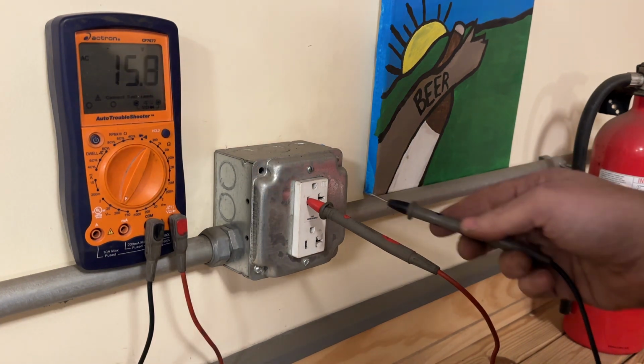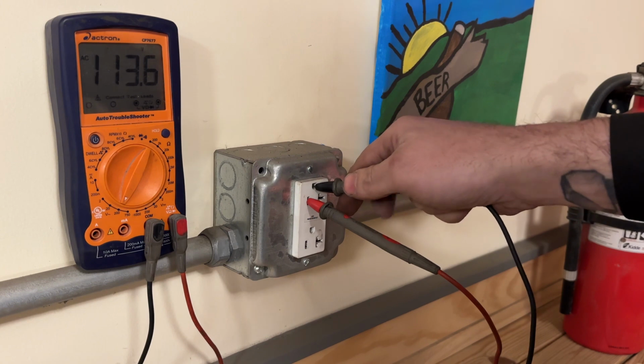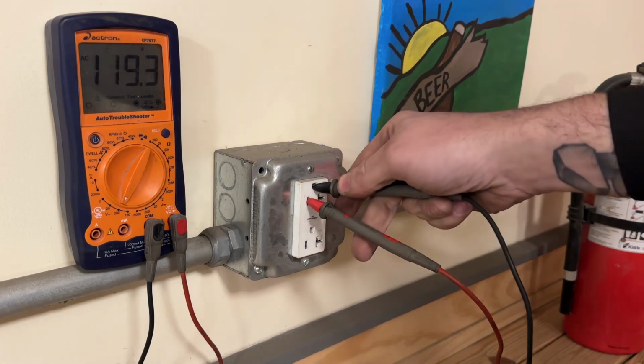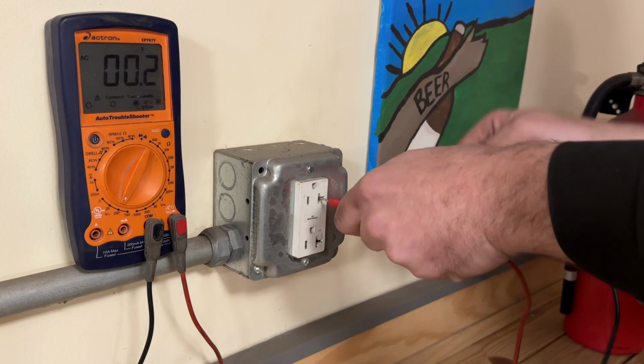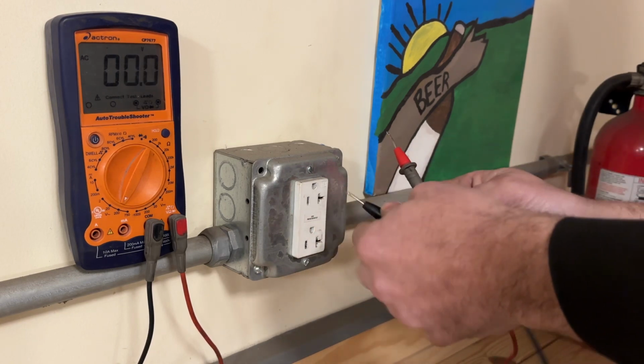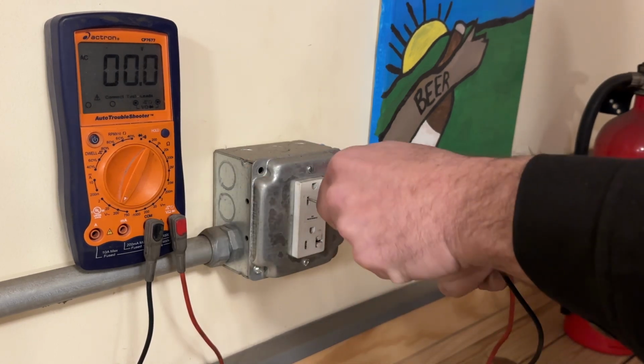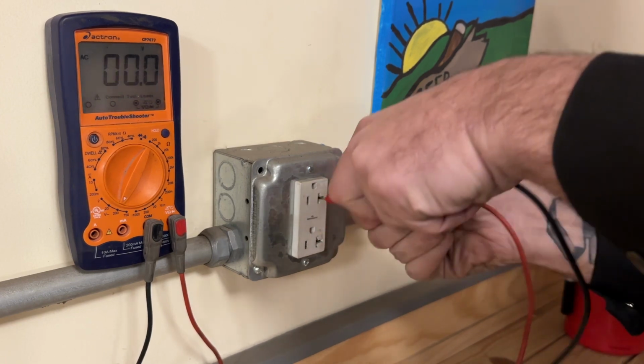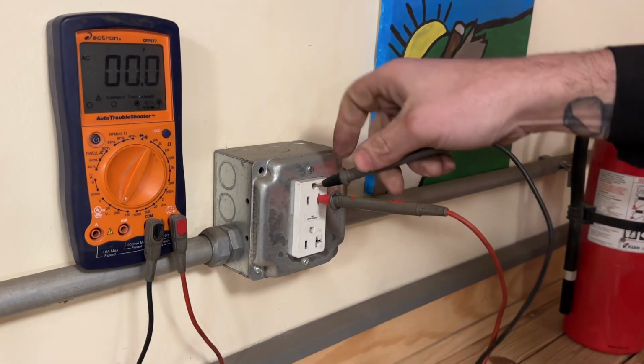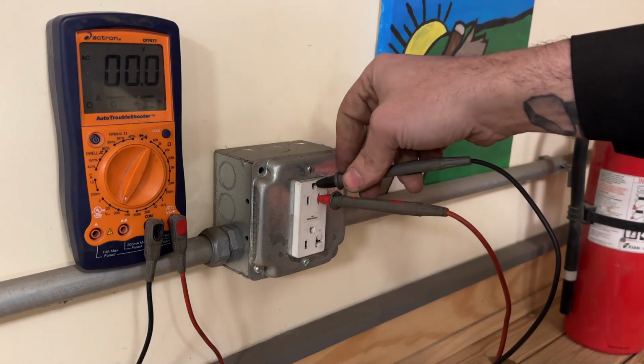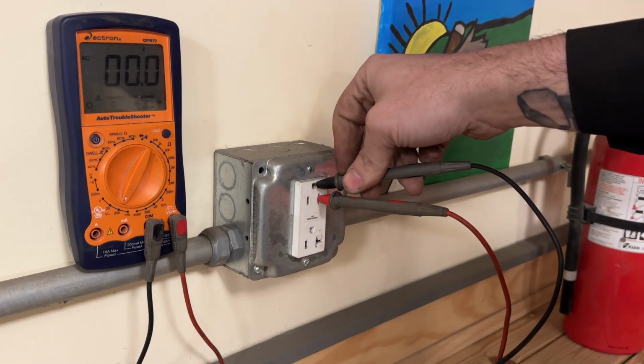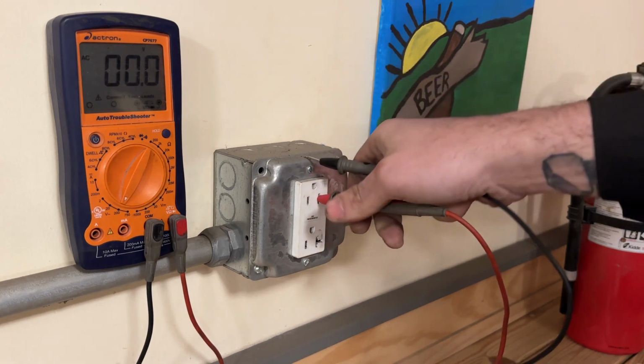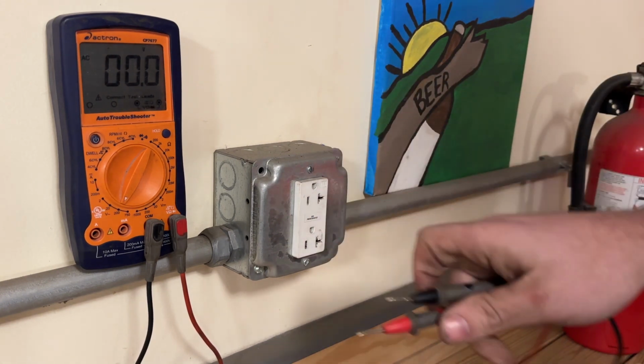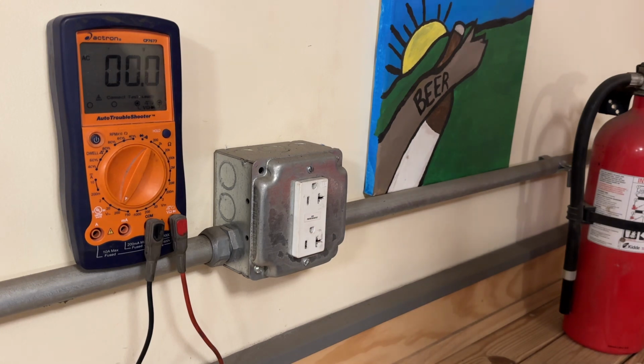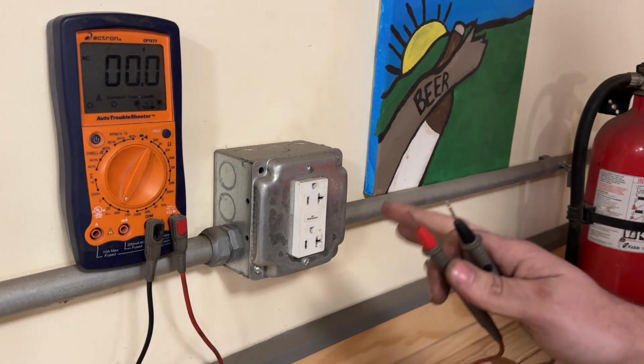This is a great way to check if an outlet is wired correctly, because between the ground and your hot should be 119 volts. Between the neutral and the ground, you should have nothing, which is what we see here, which is good. If we had power on the neutral wire, we'd have a potential issue with how the circuit's wired or what's hooked to it—could be a short, any number of reasons.